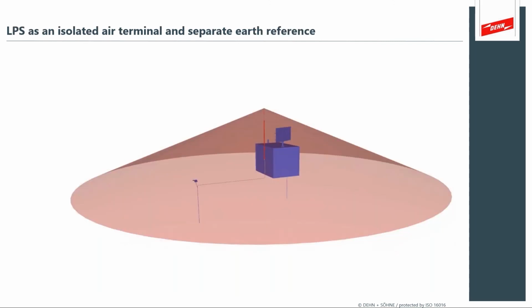We've shown in our other sessions very similar types of systems where you have an isolated air terminal that connects to the metal body but has a separate earthing system with a separate earthing reference. And we can use some of our lightning protection products that provide side flash separation distance with the ability to conduct the lightning currents into the earth separate from the grounding system of something that might look like an air traffic control radar system. And again, remember, we talked about the high intensity electric fields from radars and such, that HERF, where you don't want to have unbonded metal.